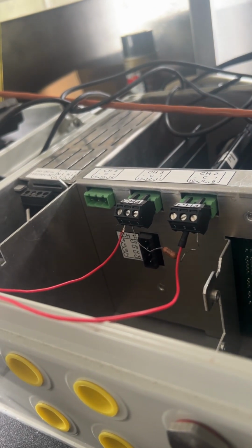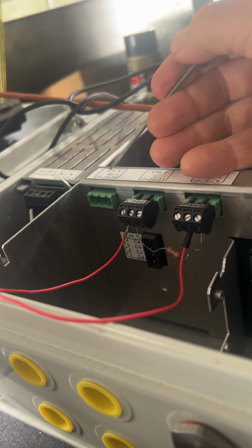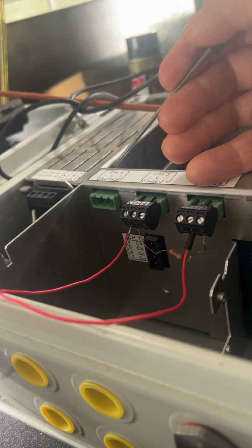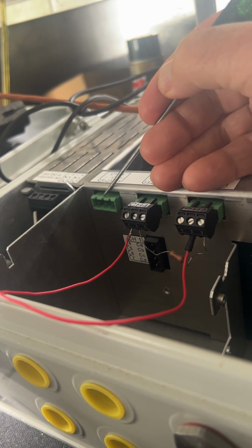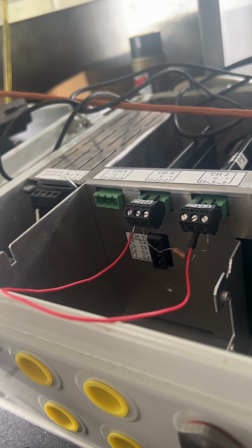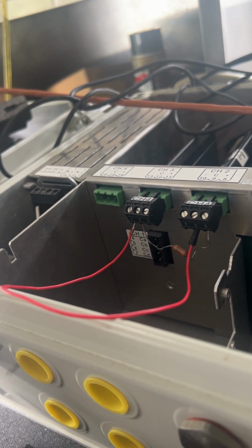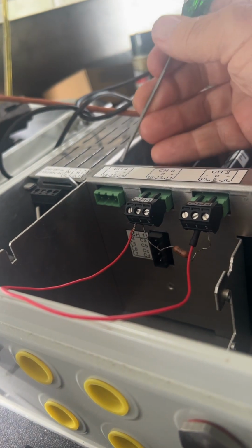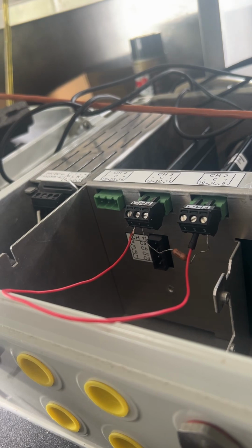And to do that, you have to add a relay and use common and minus, which is your passive input. It's just looking for a short circuit here to make this whole setup work. Unfortunately, we don't have enough signals to go around to do this without adding a relay to make the conditions for this one opposite as they are for this one.